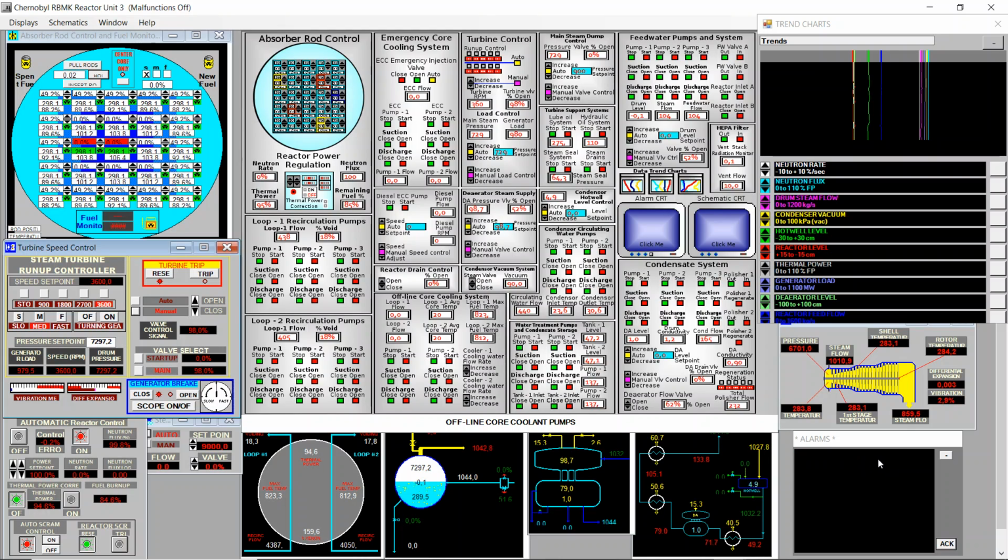It says temperature, but it means pressure. I'm pretty sure this is a mistake. And now I will keep opening the valve to 100%. Even if we have the alarm, we are not too far from the value we need, so it's fine. Okay, main valve open at 100%, power 991, but I will wait for things to stabilize.